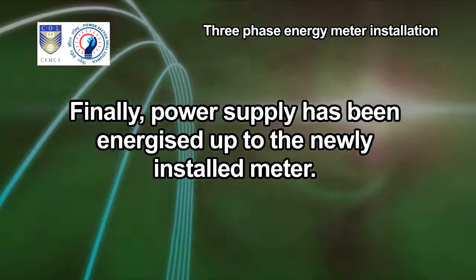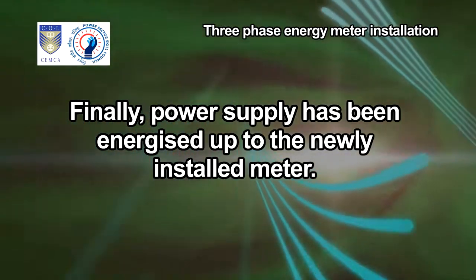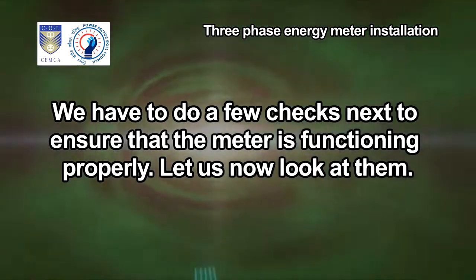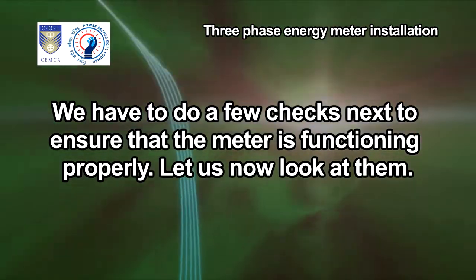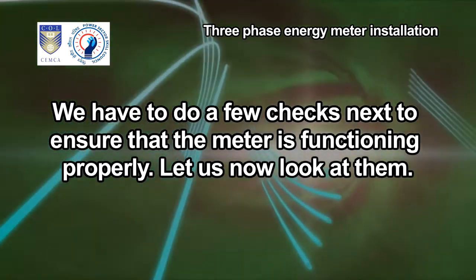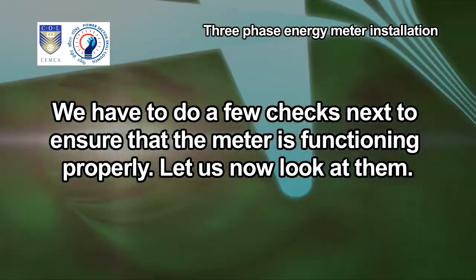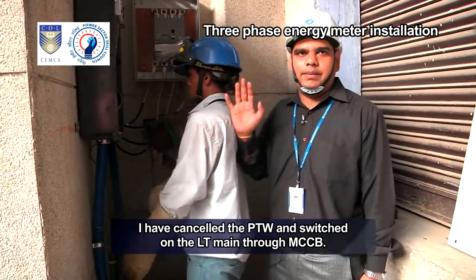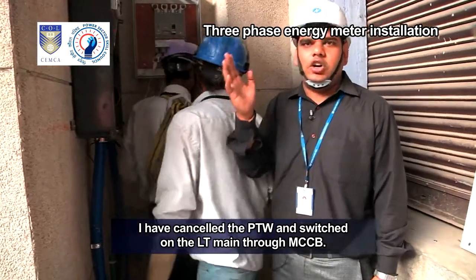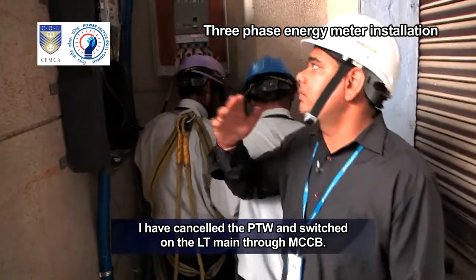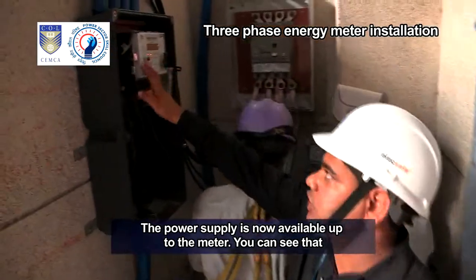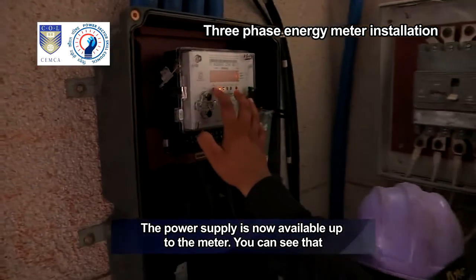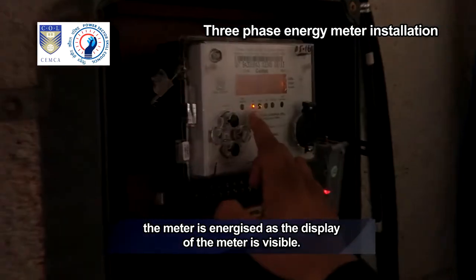Finally, power supply has been energized up to the newly installed meter. We have to do a few checks next to ensure that the meter is functioning properly. Let us now look at them. I have cancelled the PTW and switched on the LT main through MCCB. The power supply is now available up to the meter. You can see that the meter is energized.